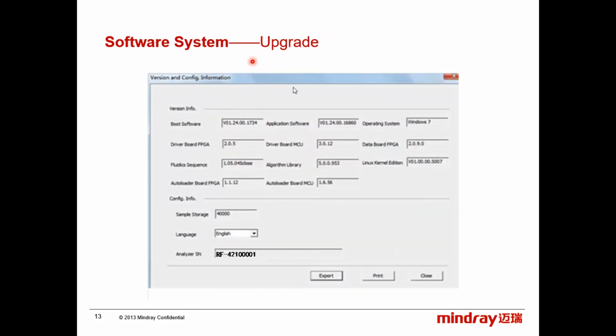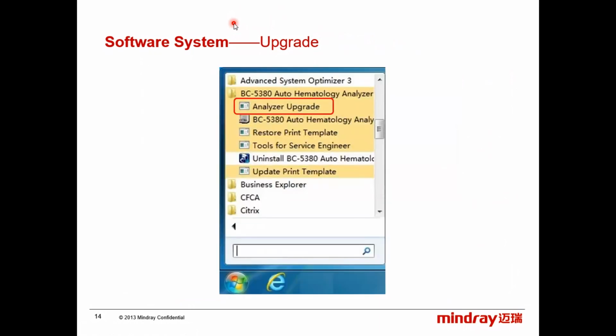Now, to upgrade the analyzer software. For this upgrade, what does it mean? Like the example I gave you during installation, or maybe you just want to install new software. When you finish installing new software on the computer, then you also need to upgrade the software of the analyzer. It has two parts: the operating system, the software of the analyzer itself inside the CPU board, and also the firmware for the FPGAs.